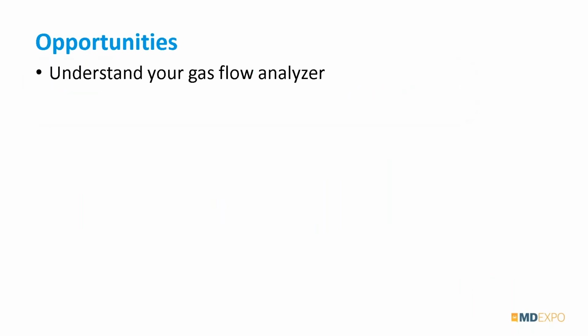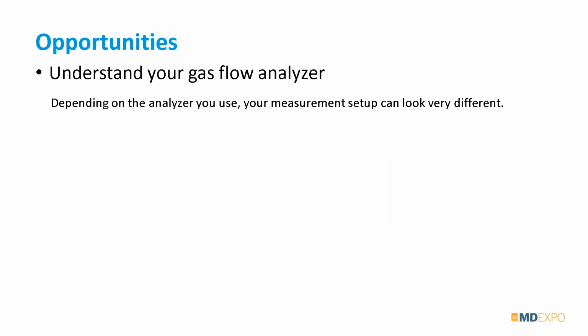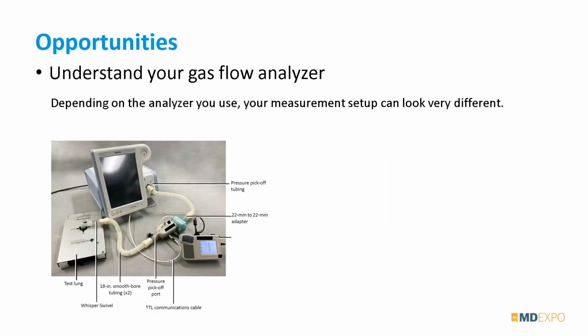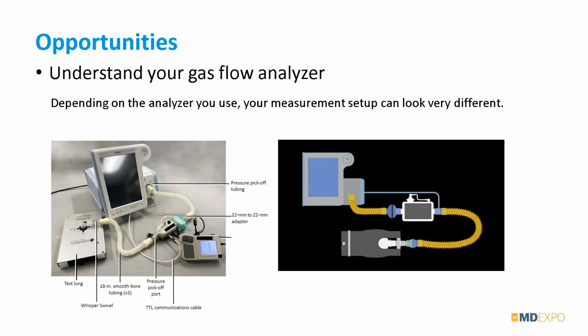The opportunity here for that challenge, of course, is learning more about your device. The more you know about it, the easier it will be to adapt to all these different situations. Questions so far? Okay. Depending on the analyzer you use, your setup can look completely different. In that first example, we show this analyzer, and we have a fairly complex setup with everything teed in. There's a tap for the pressure. Oxygen can be teed in. You might have to hook up a trigger cable to tell the analyzer when you're in inspiration or when you're in exhalation. And by using a different analyzer, you might have a much more simple setup.